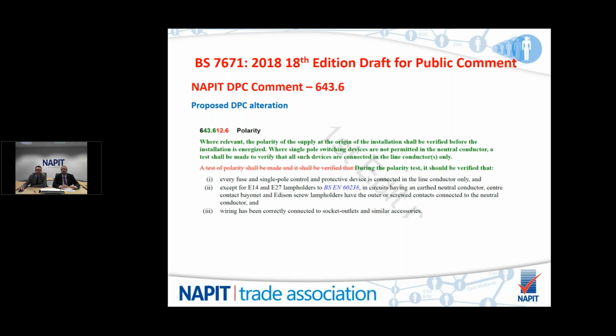And another proposed DPC alteration: polarity. So polarity, there's a big piece put in at the front there, where relevant, polarity of supply, etc. And we've got some issues with this new proposal, specifically where single pole switching devices are not permitted in the neutral conductor. They're not permitted in the neutral conductor, so why would we put that in a regulation? It's confusing. We've also got some issues with the test of polarity, where you should be carrying that out. Polarity throughout the installation, we've got some issues with that. We don't feel this DPC proposed alteration is really telling us what we want to know. So we're going to be putting forward some proposals.